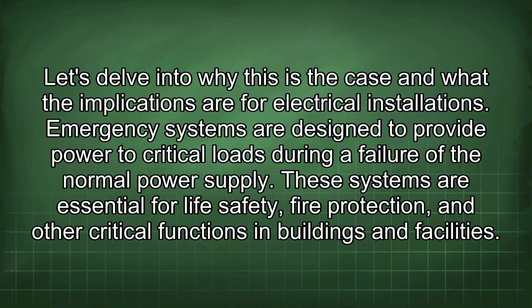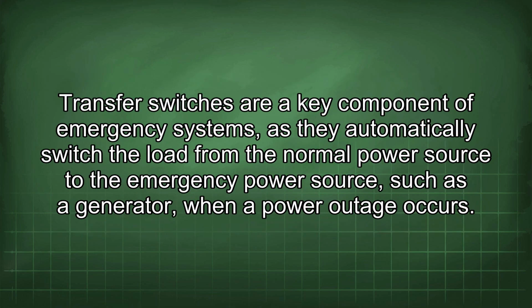Emergency systems are designed to provide power to critical loads during a failure of the normal power supply. These systems are essential for life safety, fire protection, and other critical functions in buildings and facilities. Transfer switches are a key component of emergency systems as they automatically switch the load from the normal power source to the emergency power source, such as a generator, when a power outage occurs.